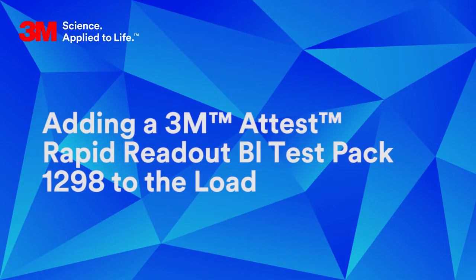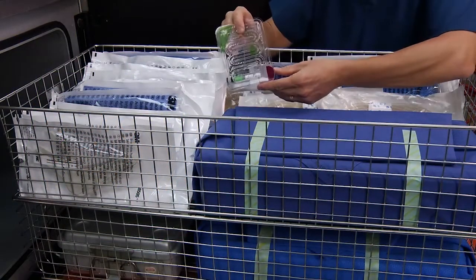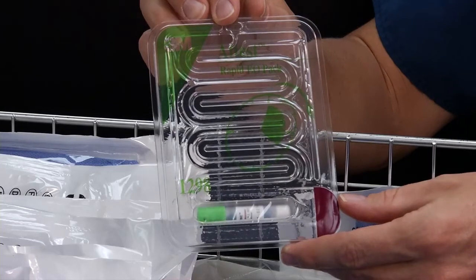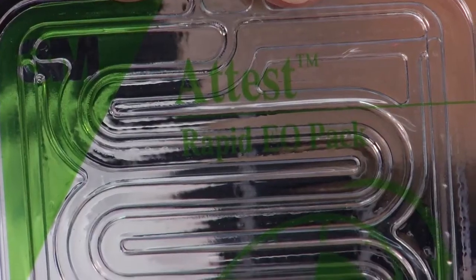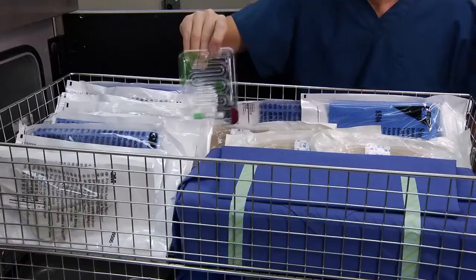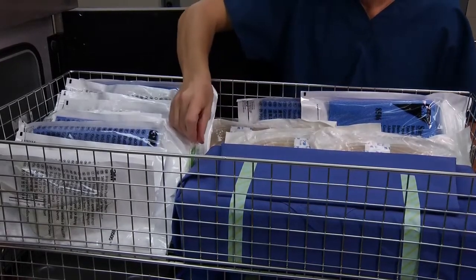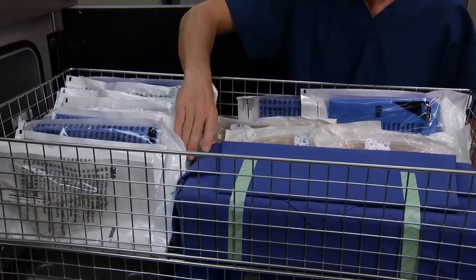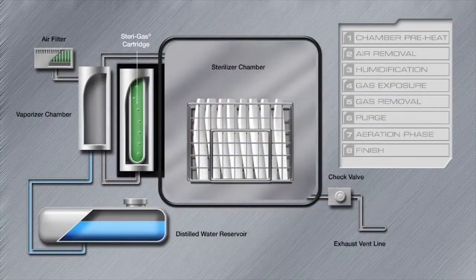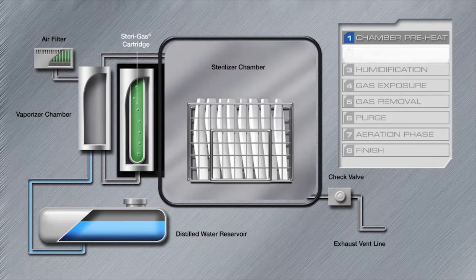Use a 3M™ Attest™ Rapid Readout BI Test Pack 1298, also known as a challenge pack, to monitor every load. Place a minimum of one 1298 test pack in the center of each load. Please note that the entire sterilization process occurs below atmospheric pressure in a vacuum within the GS series sterilizer.